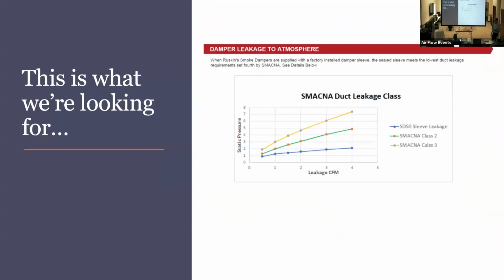Okay. Damper leakage to atmosphere. So Ruskin came out with this. Again, nobody's really talking a lot about duct leakage. However, if you want to get smart, you notice that here's a smoke damper sleeve. And we talked about high pressure ductwork, we need to be leakage class 4. So they've got a chart for leakage, not through the damper, but leakage through the side of the damper, through the sleeve. Here's leakage class 3, here's leakage class 2, and this damper doesn't leak through the sleeve. So Ruskin has this now.